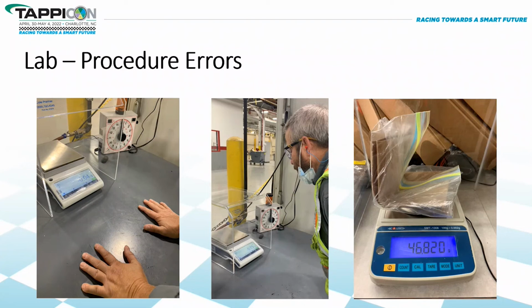If you just touch the table with your hands, the scale reading changes, as you can see here. It just varies so much. Or if you just blow air, even if you just breathe a little hard, that scale reading changes. So think about that little sample they use, a 4-inch in diameter weight sample. And if your scale is off, when you calculate your basis weight result, that could be very different compared with a true basis weight value.